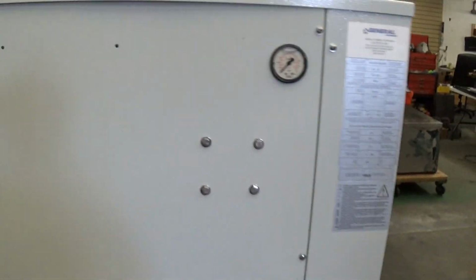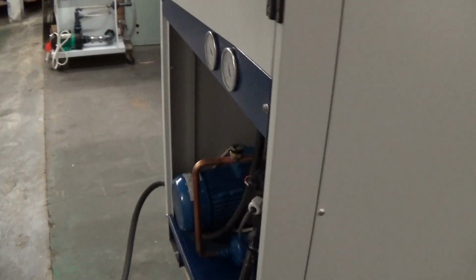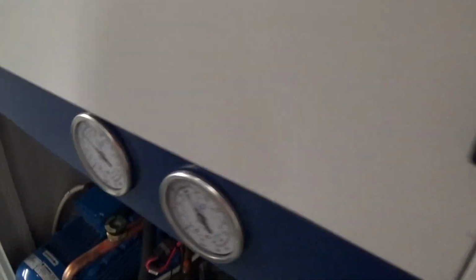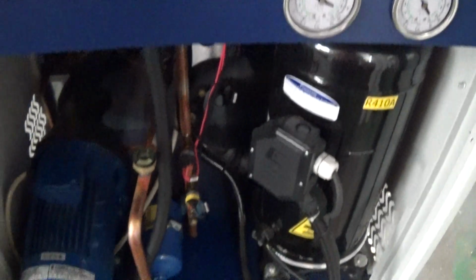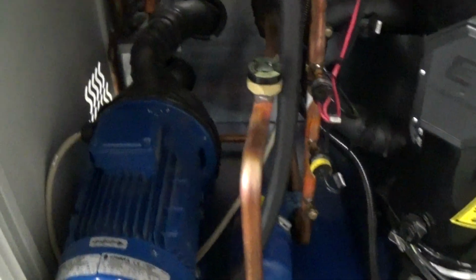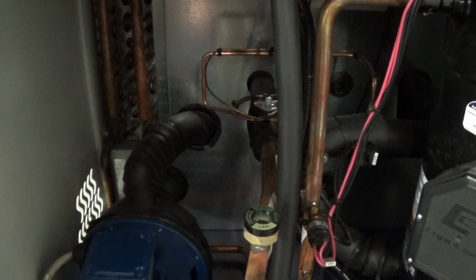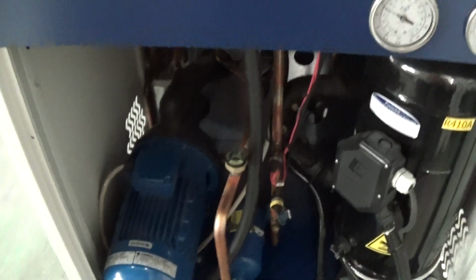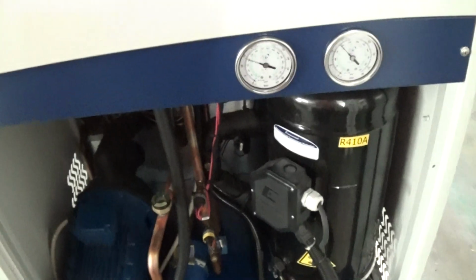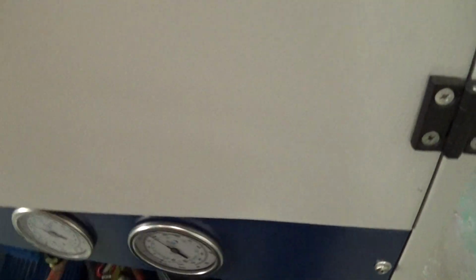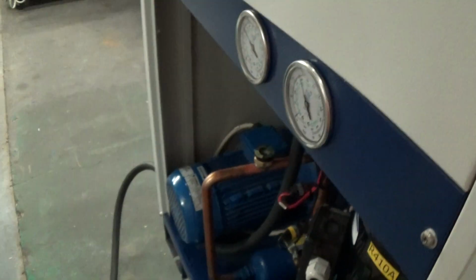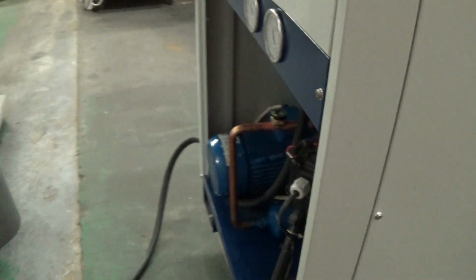It's a package chiller, meaning it has a pump and reservoir internal. This particular design, the heat exchanger evaporator, you can kind of get a feel for how clean this thing is. It's behind this wall here. I believe it's a 70-gallon tank. It's a cylindrical tank, and the evaporator is a coil type heat exchanger evaporator, immersed or submerged inside that tank.